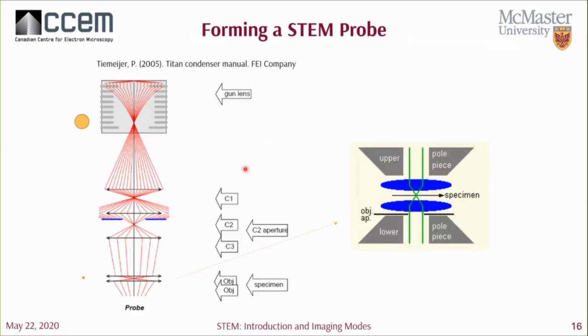So overall, the goal here is to demagnify the beam of electrons emitted from the electron source to a point on our specimen. A beam of electrons emitted from the source gun can have a crossover diameter of about several nanometers. So we'll need to demagnify this source, or this image, to a point, and we can do so in the microscope using the condenser lenses and the objective lens systems.